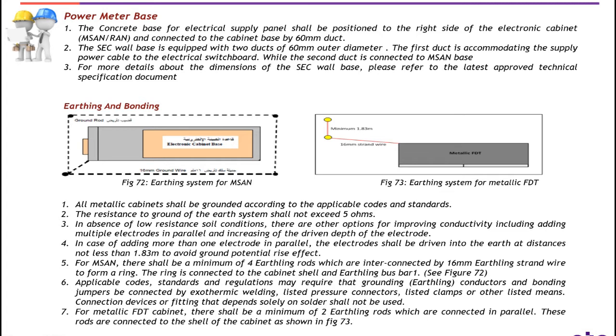Power meter base — there are a number of checkpoints. Number one: the concrete base for electrical supply panels shall be positioned to the right side of the electronic cabinet — we call it MSAN or RAN — and connected to the cabinet base by a 60 mm duct. The SEC wall base is equipped with two ducts of 60 mm outer diameter. The first duct accommodates the supply power cable to the electrical switchboard, while the second duct is connected to the MSAN base. For more details about dimensions of SEC wall base, refer to the latest technical specification document.